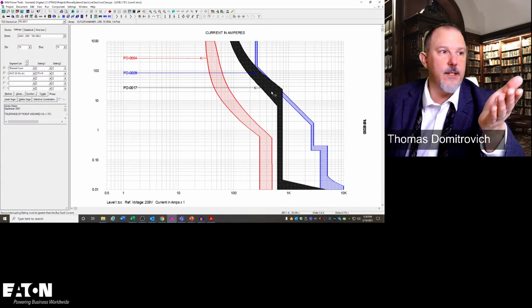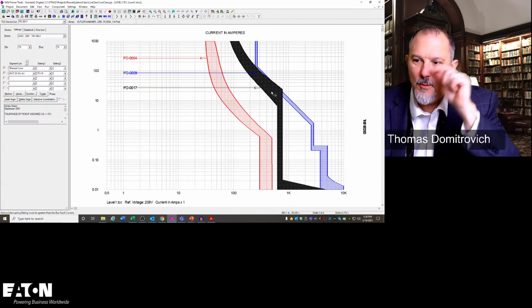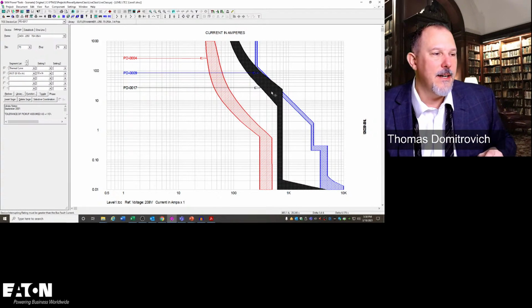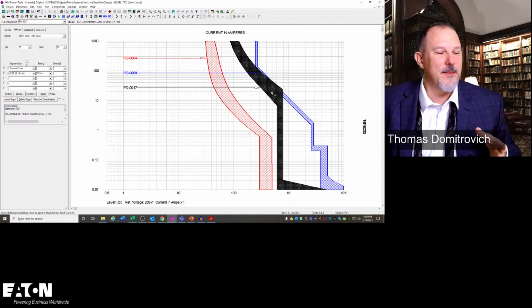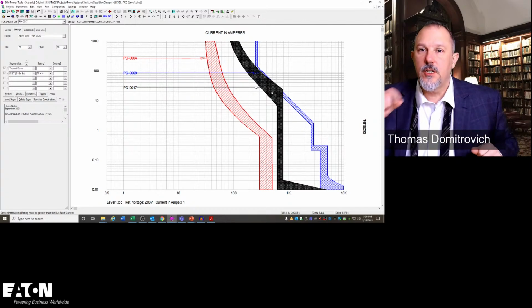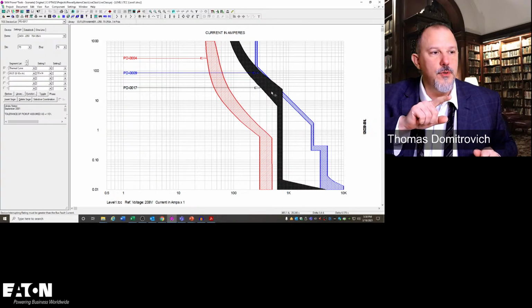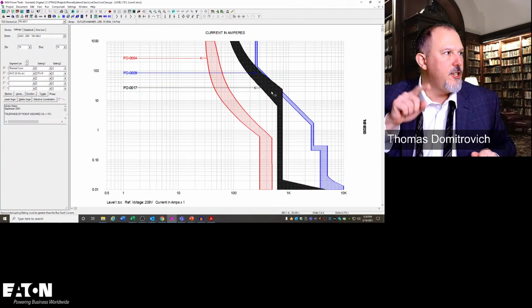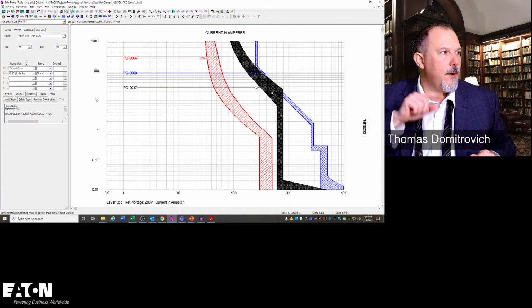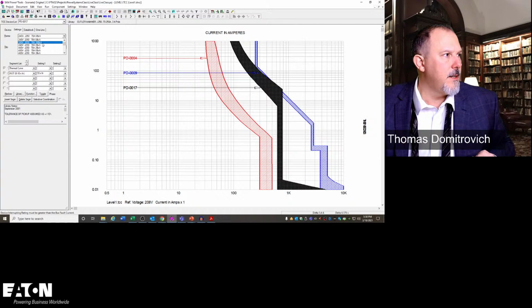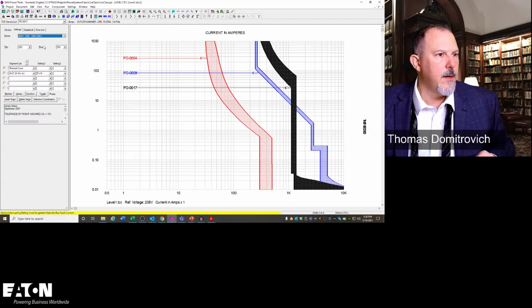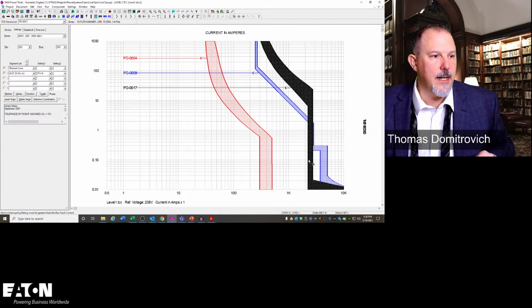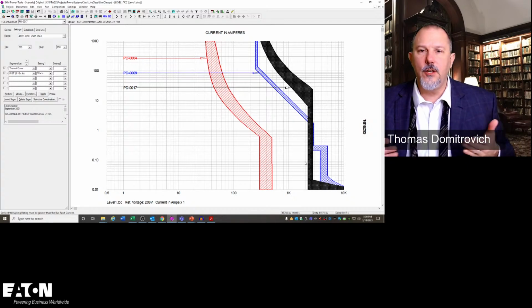Okay, so I could have done this with a 110.4. Sweet. The delay time is good. There's very little delay between us and YouTube. So why wouldn't I use a J250? This is a 250. That's 70 amps. Hold on, I've got to get this up to 250, right? 250, right there. Look, there's my 250. Look at this. And I can move the instantaneous way out there.